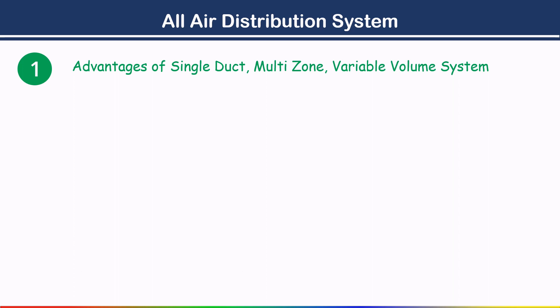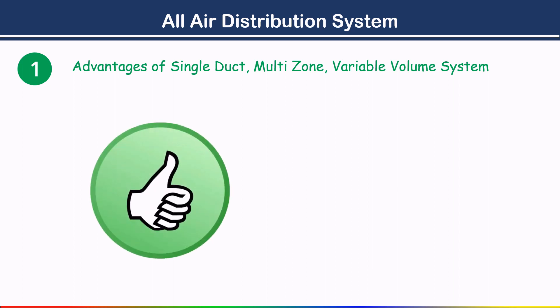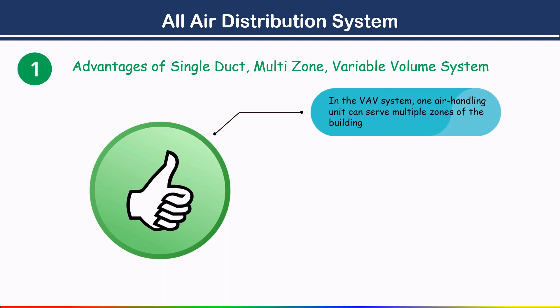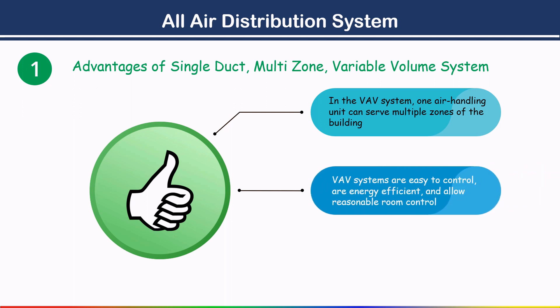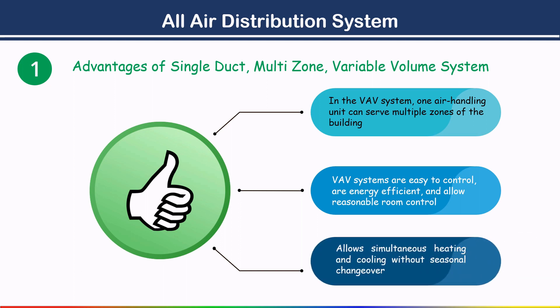Advantages of the single duct multi-zone variable volume system: First, one air handling unit can serve multiple zones of the building. Second, VAV systems are easy to control, energy efficient, and allow reasonable room control. Although the initial cost is higher than a CAV system, the running cost is low. Additionally, this system allows simultaneous heating and cooling without seasonal changeover.